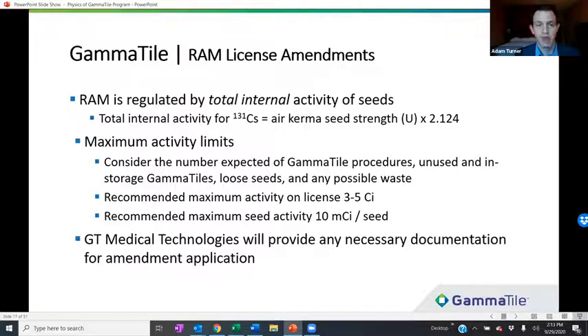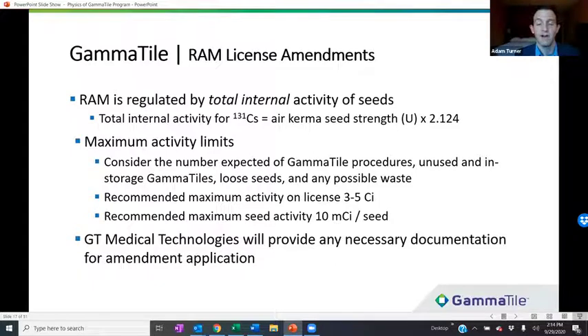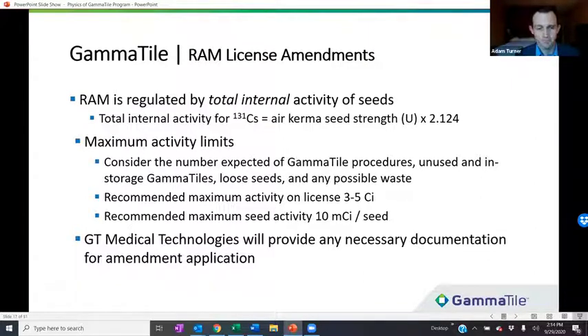When doing a license amendment, you're typically tasked with specifying the maximum activity of a given isotope you could have at your site. Consider the number of expected Gamma Tile procedures as well as any potential unused tiles in storage, loose seeds, and possible waste. For a larger site, we recommend a maximum activity request of about three to five Curie. It's also typically necessary to request a maximum seed activity — we recommend about 10 milliCurie per seed. GT Medical Technologies is here to help with any necessary documentation for your amendment application, so don't hesitate to reach out.